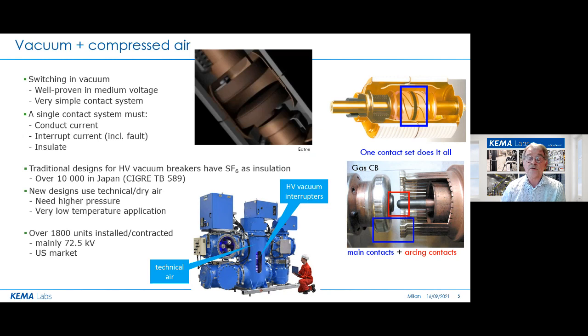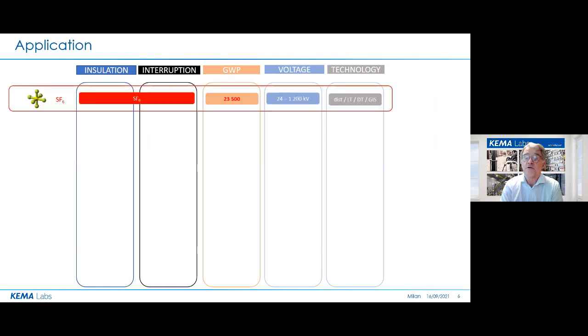Well, let's go over to the gases now. So the pillars of switching technology are insulation, interruption, rated voltage, and technology. Well, now a new one jumps in, which is the GWP, because that is becoming more and more important these days. Well, first, we all know SF6. SF6 is Mr. Do It All. It is applied from medium to ultra high levels of voltage up to 1200 kV and is able to deal with fault current of 300 kA and more. It is also available in all technologies. So it's live tank, dead tank, GIS.